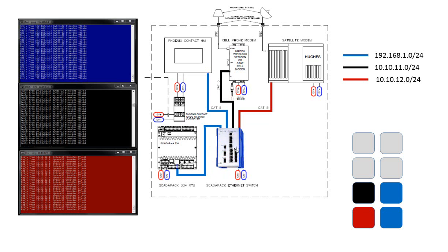In this case, I've got the RSP. This particular model is the RSP 35, I believe. It is a layer 3, which is going to facilitate me to do this routing. This application is for pipeline valve monitoring. So we've got a SCADA pack here, an RTU, we've got an HMI. The whole lot is powered by what appears to be some solar cells, so they have a 12 to 24 volt converter. These two devices then need to talk to either a cell modem, or if the cell modem is out, to a satellite modem. So there are two wide area network connections in this control box.